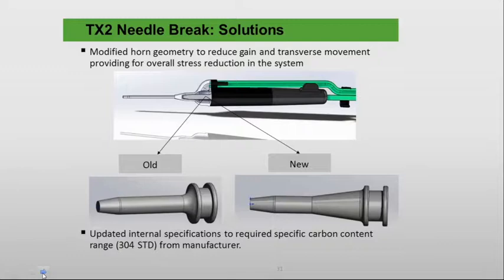tolerances to handle the amount of stress that it would be exposed to, as so often happens in the clinical realm, we were seeing a highly unacceptable rate of fracture of the probe. And just so you know, some of those on the webinar tonight probably experienced that. The sinister part about it is you can pull the sleeve out and the probe would still be left deep in the wound, and in one or two instances it may not have been recognized, or if it's recognized, it's not sticking out through the skin, so there's an additional effort to treat it. So it was in fact a major issue.